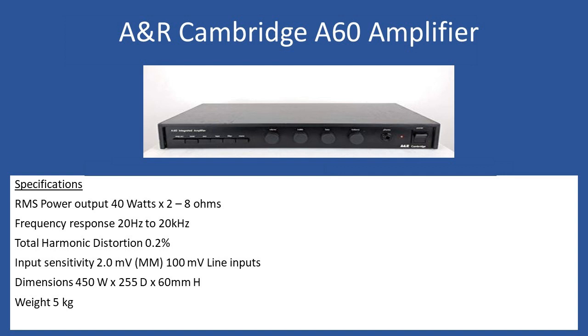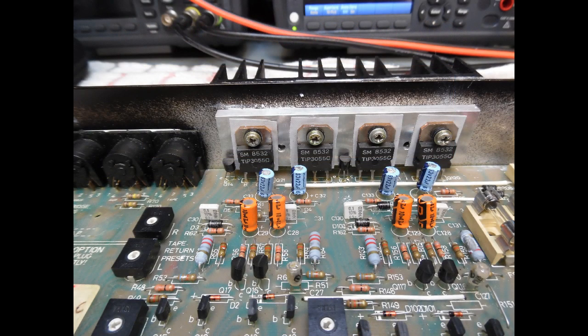So what was the issue with this amplifier? It came in from the customer, who outlined an issue with the secondary power supply fuses failing. These are rated as fast blow, 3.15 amp, and it was blowing these fuses on power up.